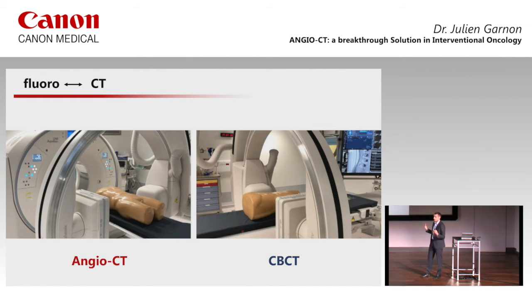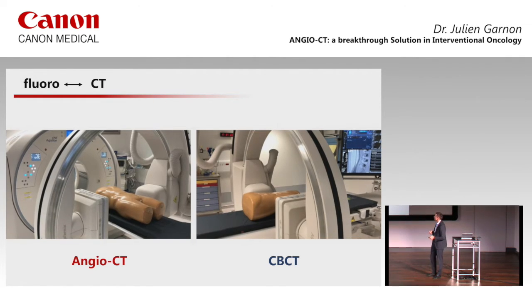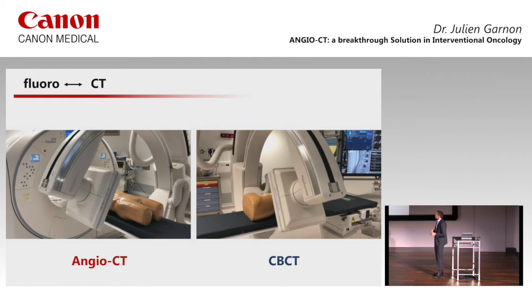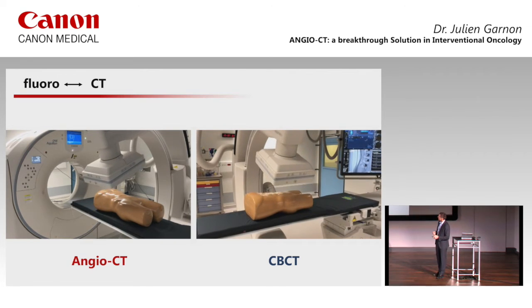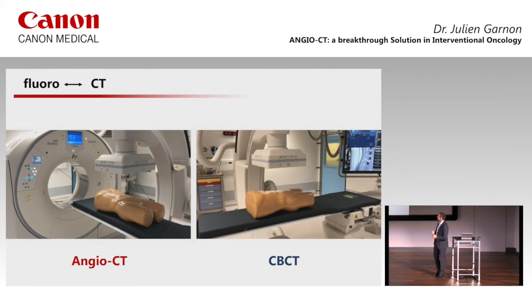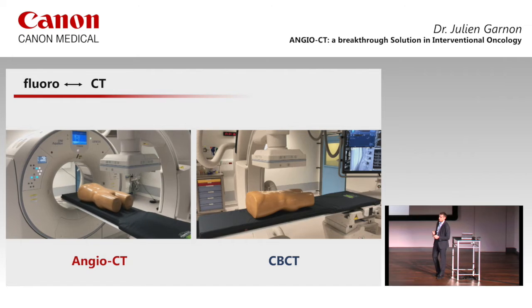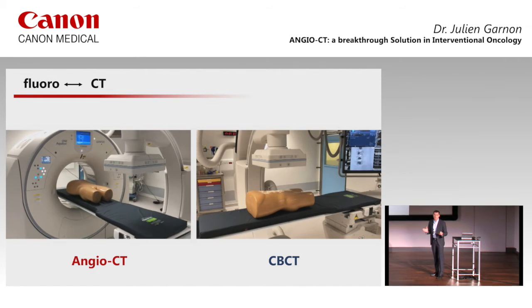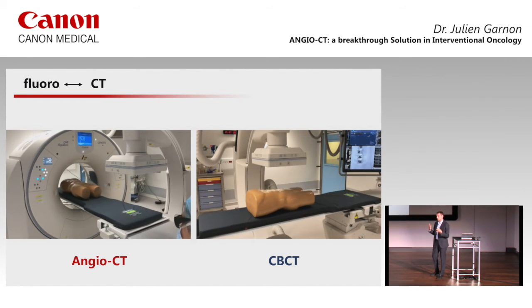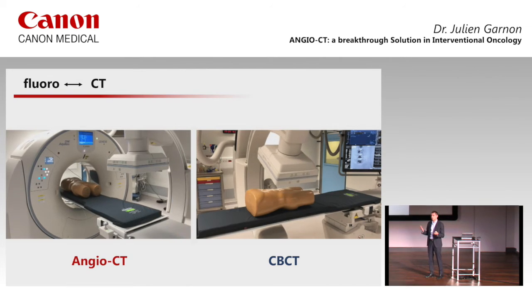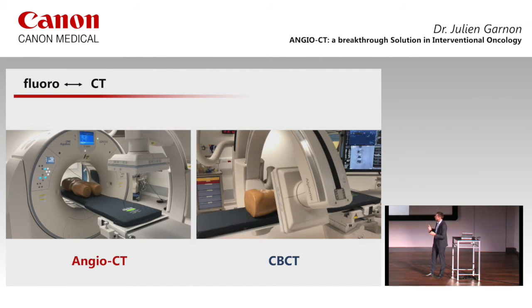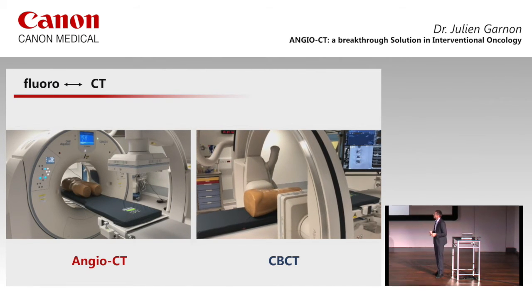And if we start during the same time, on the left side you have the Angio-CT, on the right side you have the cone beam CT, you will see the difference. With Angio-CT, you have to put the arm up, you go to the CT scan, less than 30 seconds, and you are ready to get the images. And once you press the button, in 1 second, you will have the images, 1 to 10 seconds, depending on which sequence you are using.